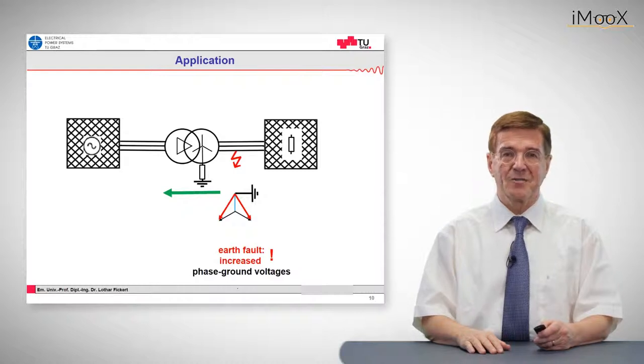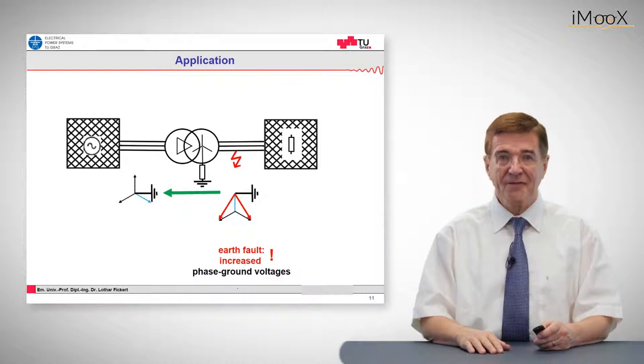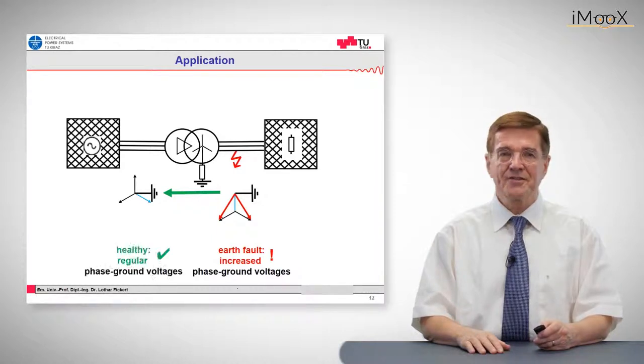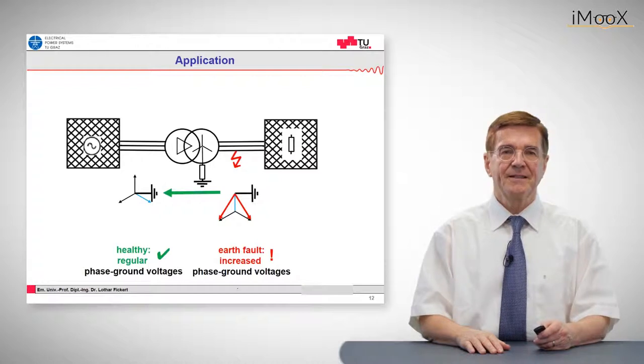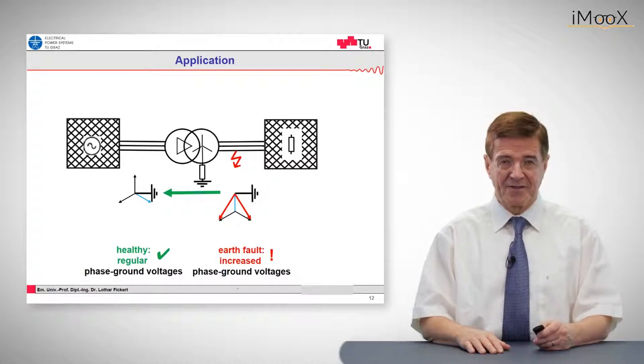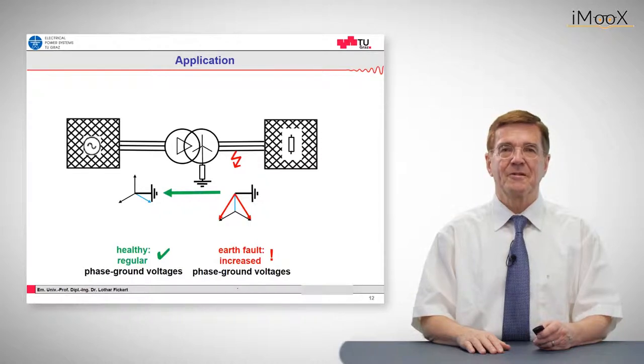which in this case is delta y. So if you have a delta y transformer, the primary side voltage is not disturbed, not afflicted by this fault, and we have healthy and regular phase to ground voltage. And this is the reason why we have transformers with different and adjusted vector groups.